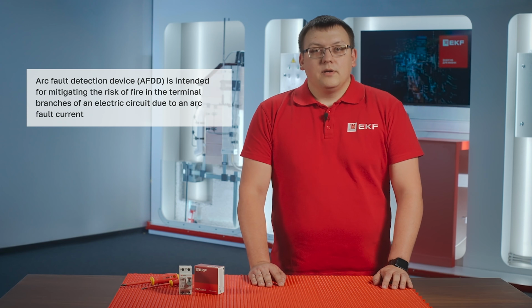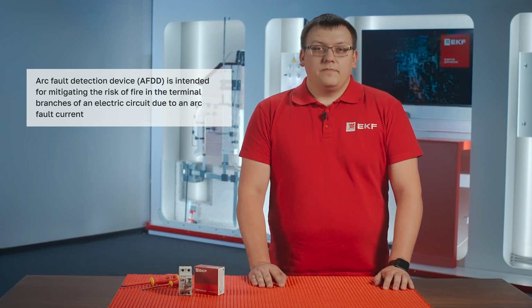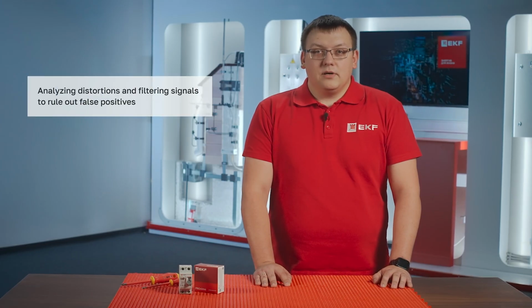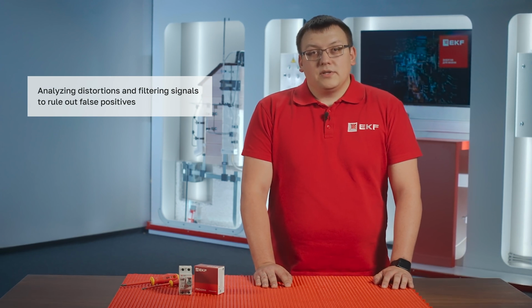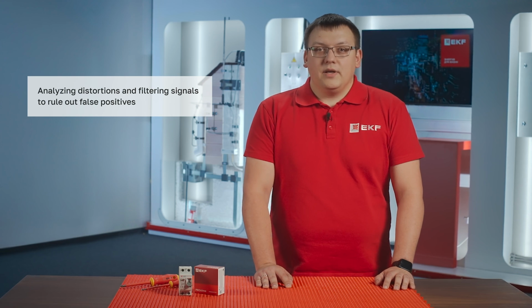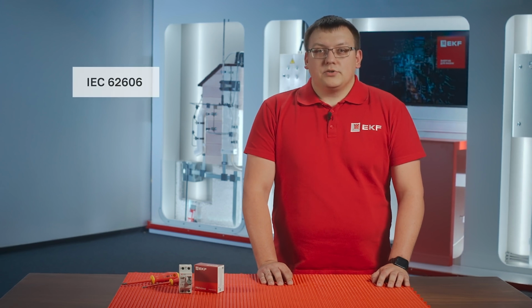So what is AFDD? An arc fault detection device is intended for mitigating the risk of fire in the terminal branches of an electric circuit due to an arc fault current that in certain conditions, for example, prolonged arcing, may cause a fire. AFDD is a microcontroller device that enables detection of hazardous sparking or arcing using a special mathematical algorithm that can happen due to faults in 230-volt 50 Hz alternating current circuits and electrical appliances. Analyzing distortions and filtering signals to rule out false positives. Arc welding, switched mode power supply units, LED lighting, brushed motors, etc. Isolation of protected circuits from the rest of the power supply in the event of sparking to prevent fires. AFDD complies with IEC 62606 requirements.